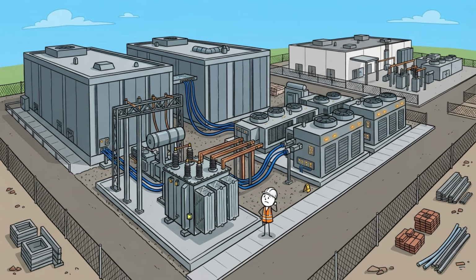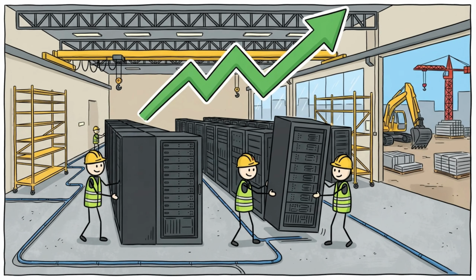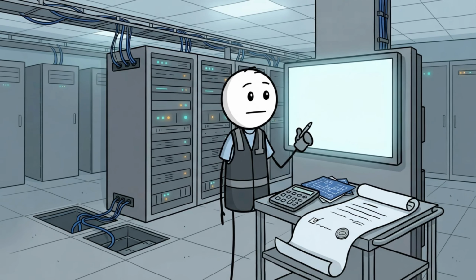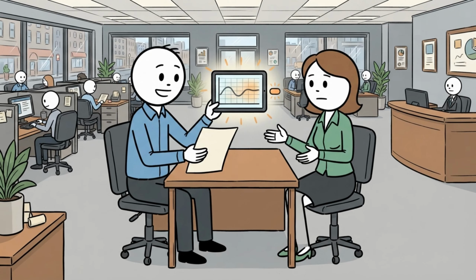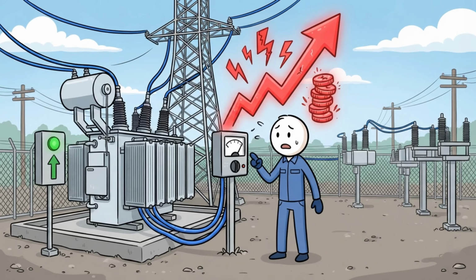Historical data shows only about 19% of projects entering U.S. interconnection queues between 2000 and 2019 had reached commercial operation by the end of 2024. This can end a developer's entire project in a single event: a loan covenant tied to a commercial operation date that the local grid operator, not the developer, ultimately controls.